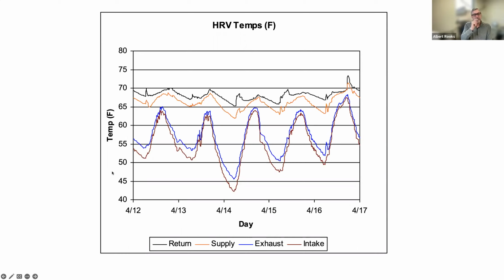And the interesting thing is that you can see a little blip on the black line and the orange line, like every day. There's a little tiny peak there. And what that peak actually represents is, it's a funny little thing. That is actually the morning shower. So when you think about the morning shower, it's an event where you go into a bathroom, which usually has a ventilation duct to pull air out and send it to the HRV for heat recovery.